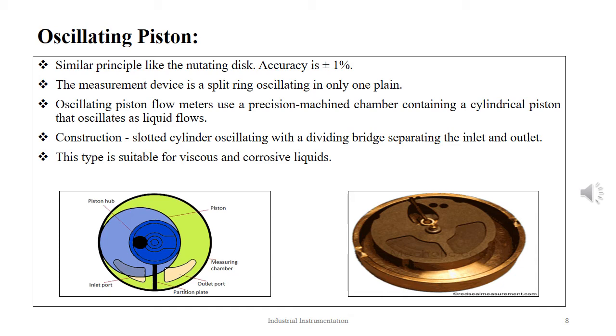Initially, the piston rests at the central position. As fluid enters the section, the ring starts rotating from left to right until the fluid is escorted to the outlet. The rotation of the piston is transmitted through a diaphragm to the gear train and is registered. This type is suitable for viscous and corrosive liquids and the accuracy offered is ±1%.